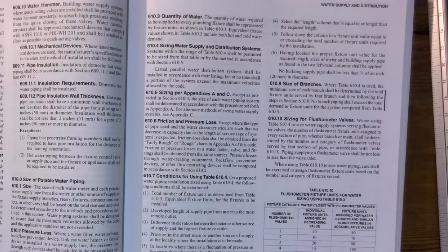And then we select the length column that's equal to or longer than the required length. Equal to or longer than the required length. That's the column we have to pick. So if I have a total developed length of, we'll say, 96 feet, we can't use the 80-foot column. We have to use the 100-foot column.